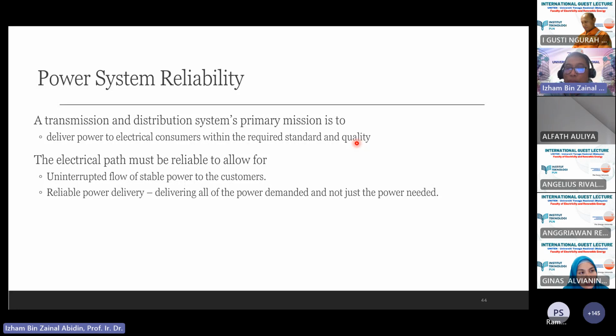And of course, quality, maybe there is a specific harmonic content that cannot be there. This is particularly important for distribution system because harmonic comes from motors and machines. So therefore, if you don't control harmonic in your power supply to the distribution system, your supply is not of good quality. When it is not of good quality, it means that if you have sensitive equipment, it may not function properly and it can also damage the equipment.